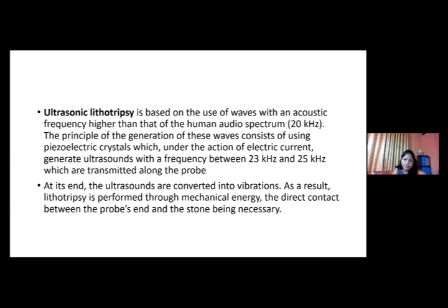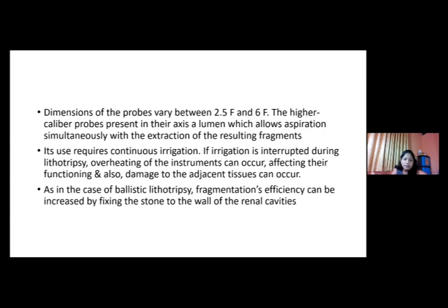Then ultrasonic lithotripsy. Ultrasonic lithotripsy uses ultrasonic waves created using piezoelectric crystals under the action of electric current. These frequencies are far beyond the normal audible spectrum, about 23 to 25 kilohertz. The ultrasound waves create vibrations, and this vibrational energy is converted to mechanical energy to fragment the stone. The main problem is that we need continuous irrigation, because it can cause overheating and damage to the instrument and adjacent structures.